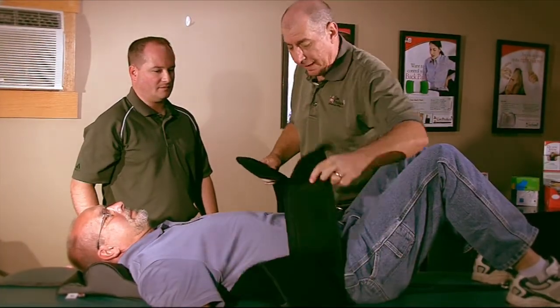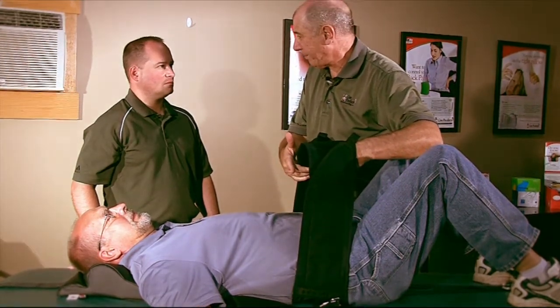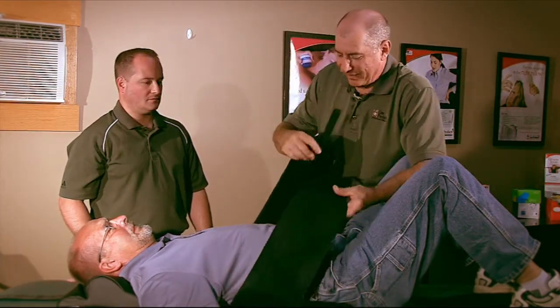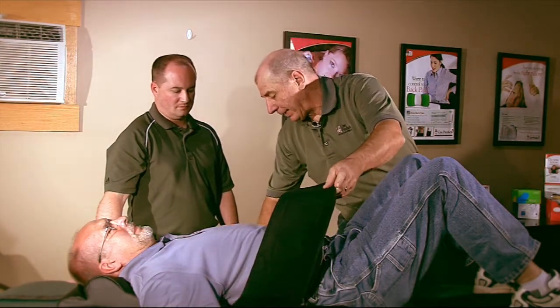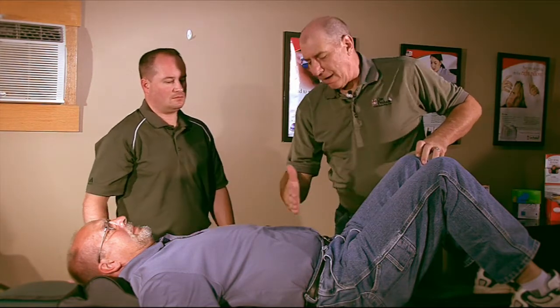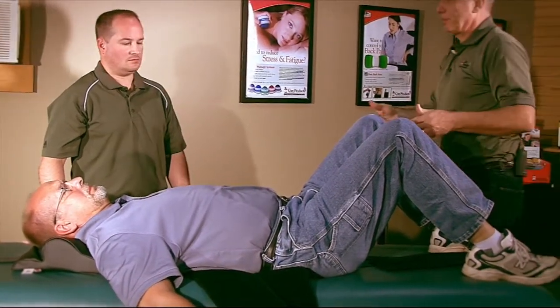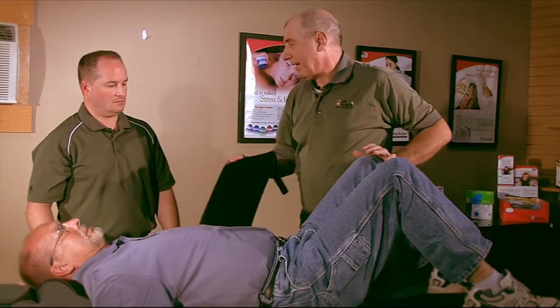So Jason, if we had a much larger patient that had more girth, we could simply place the extender in. This would go up to, I believe, pushing 60 or so inches for a waist size. Now one of the things that's been asked is, do we have one for the upper piece? The thing is, if someone is much larger than this, the way we have the non-slip material both against the patient and against the table — let's say this was a 300-pound patient. About half of that body weight is on this side of the table, so that's 150 pounds pushing down on a non-skid material. We're going to apply 60 or 70 or 80 pounds this way, and the math does not work out that 60 or 80 pounds is going to pull those 150 pounds down — so you probably wouldn't even need the upper belt.